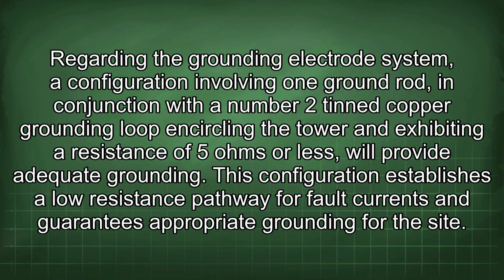Regarding the grounding electrode system, a configuration involving one ground rod, in conjunction with a number 2 tinned copper grounding loop encircling the tower and exhibiting a resistance of 5 ohms or less, will provide adequate grounding. This configuration establishes a low resistance pathway for fault currents and guarantees appropriate grounding for the site.